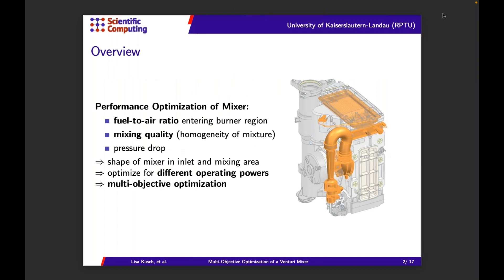You can see the system on the right-hand side. We are specifically interested in the Venturi mixer, where methane and air are mixed before they enter the burner region. We want to optimize the performance of this mixer by optimizing its shape. We are interested in different performance measures: first, meeting a target fuel-to-air ratio before entering the burner region; second, improving mixing quality in terms of homogeneity; and at the same time, constraining the pressure drop in the system.